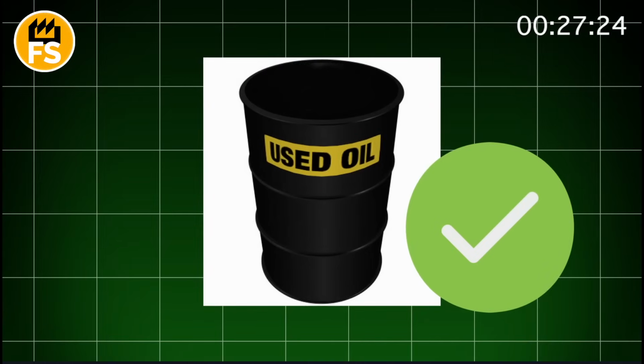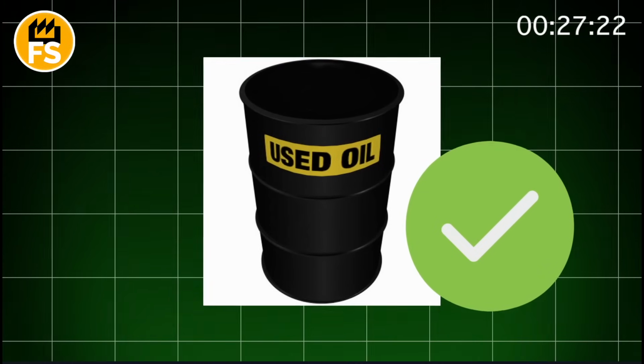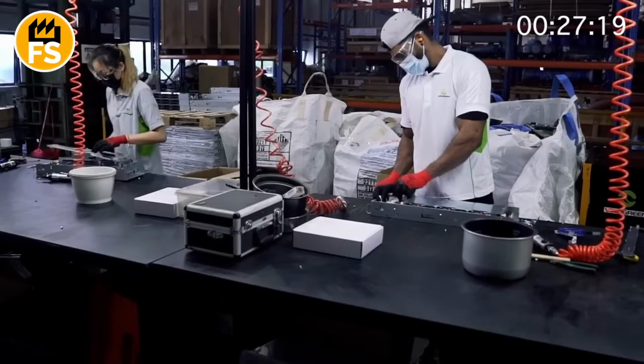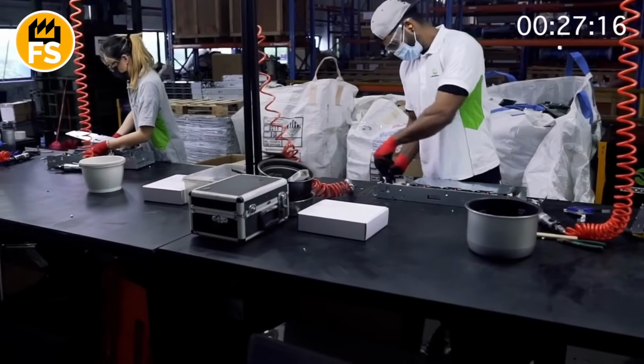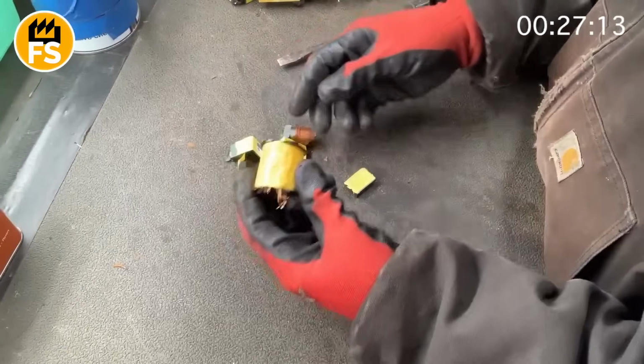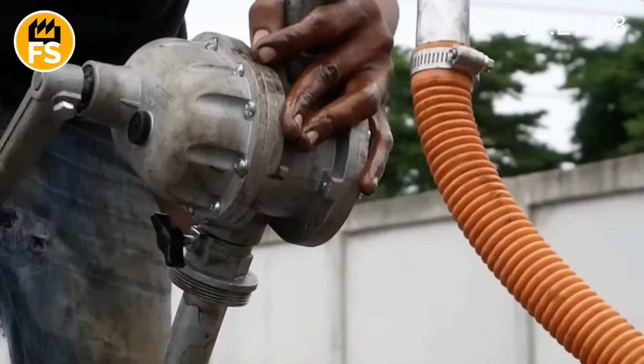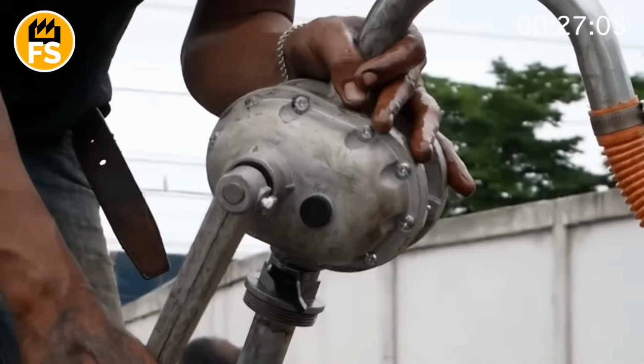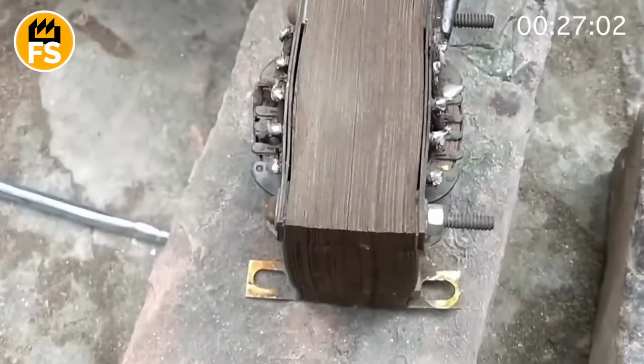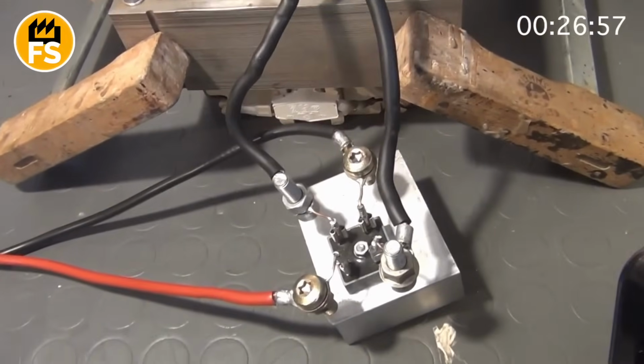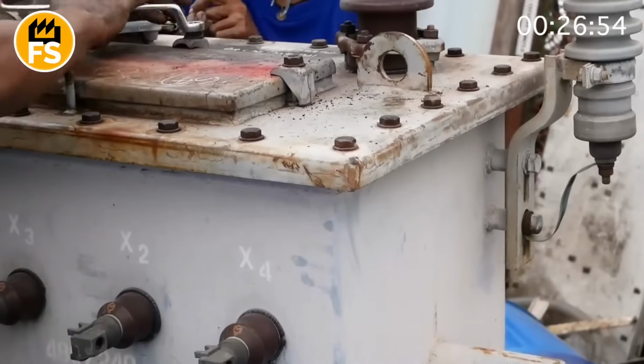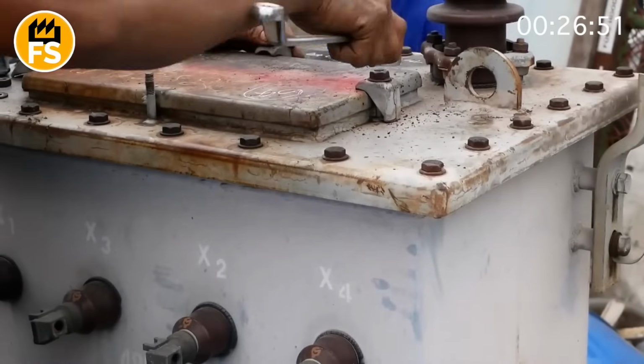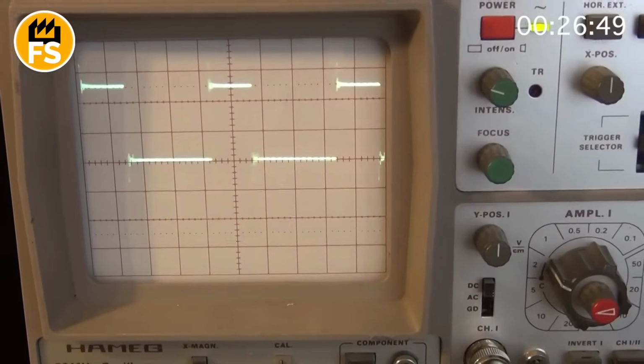After every drop of oil is confirmed, safely drained, and contained, the transformer must be absolutely de-energized and rigorously verified as safe from any residual electrical voltage. Even units that have been disconnected for years can potentially hold a dangerous charge. Highly trained technicians follow strict, multi-step lockout, tagout, and grounding procedures, physically isolating the unit and discharging any potential buildup to ensure no electrical hazard remains before any physical dismantling tools come anywhere near the unit. Safety protocols here are layered and redundant, because any mistake made at this stage carries the risk of severe injury or worse.